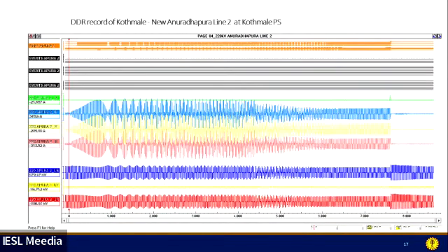This is the snapshot taken from the records of the line current waveform of the line Kothmale to New Anuradhapura. So these are the power oscillations observed in the digital disturbance record in this particular line. The current waveform increases like this for about 5 seconds. After that, there's some steady period, but at the end, the distance relay tripped at this point. But by that time, almost all the system power generators had collapsed, and this tripping is not a contributory factor for the total failure, because by this time, all the generators had tripped.